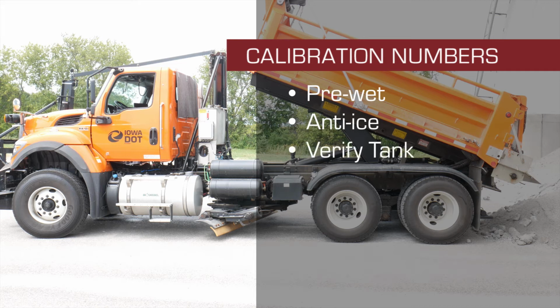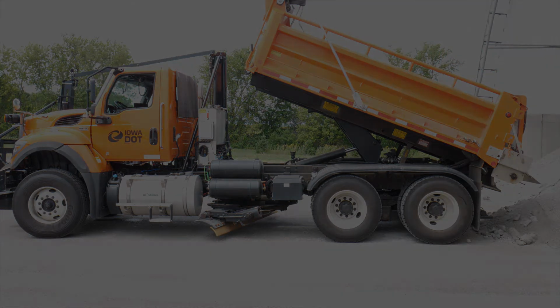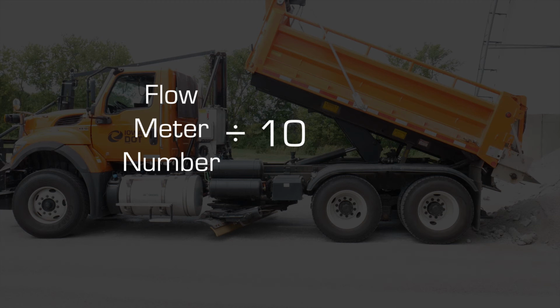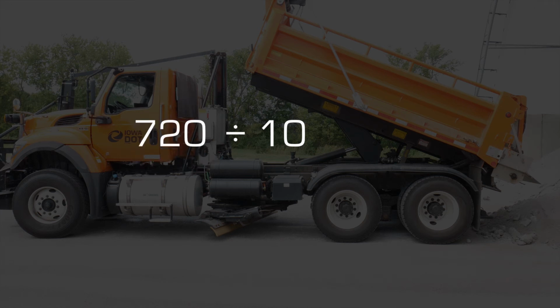Make sure that the flow meter you are looking at is connected to the tank of material you are currently calibrating for. Divide the flow meter number by 10. For example, if the tag reads 720, the value you will enter will be 72.